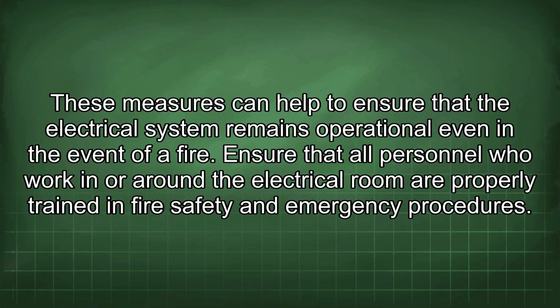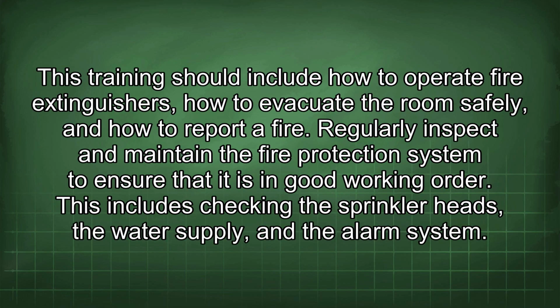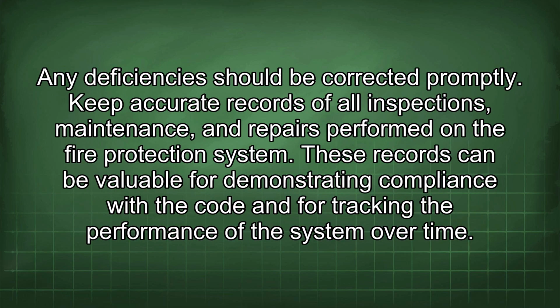Ensure that all personnel who work in or around the electrical room are properly trained in fire safety and emergency procedures. This training should include how to operate fire extinguishers, how to evacuate the room safely, and how to report a fire. Regularly inspect and maintain the fire protection system to ensure that it is in good working order. This includes checking the sprinkler heads, the water supply, and the alarm system. Any deficiencies should be corrected promptly.